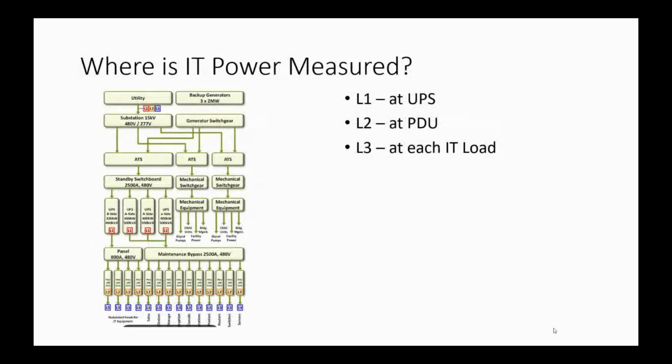Okay, so I talked about measurement, and I said only data center measured PUE should be allowed to report. Okay, where exactly do you measure in the data center? That again is a question that we need to answer. The specification actually allows you to measure it. So incoming power, data center incoming power, that's easy, right? Some utility company is providing power into your data center. You measure how much power is coming in. That's one place you just measure it, you're done.